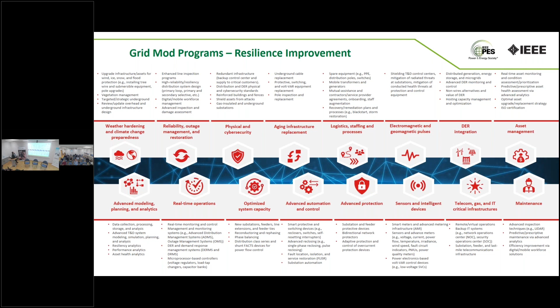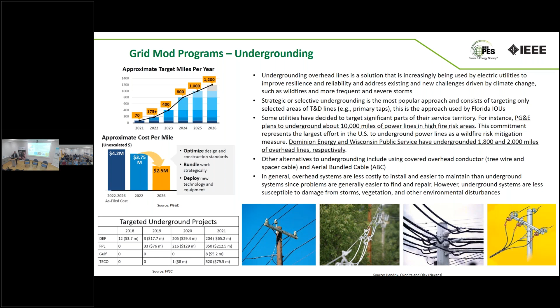Undergrounding is a big initiative, strategic undergrounding in the U.S., to improve resilience, and some utilities have proposed quite ambitious programs. PG&E is one of them, but more recently, in the last month or so, there are some issues about this. The Commission is questioning the need to underground this amount of miles of power lines to improve resilience. In their case, they have issues with wildfires. Another utility in Southern California is proposing, instead of undergrounding, to use aerial insulated cable, aerial bundle conductor, and other types of insulated cable. The idea is, if there is contact from vegetation, to prevent an arc, because that arc can create a wildfire.